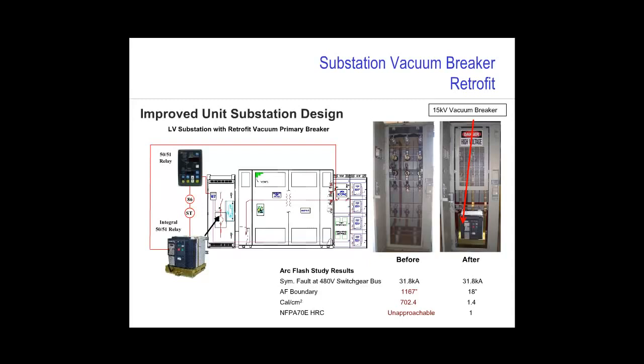So they decided to move forward with some of the new technology we've shown you, installing a miniature vacuum circuit breaker with an integral trip unit in the primary of the substation, essentially replacing the switch but leaving the load break disconnect in the primary assembly. It's interesting to note that this breaker is actually tripped from two different places.